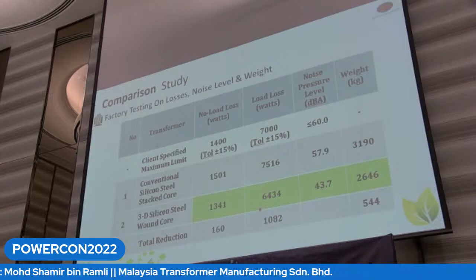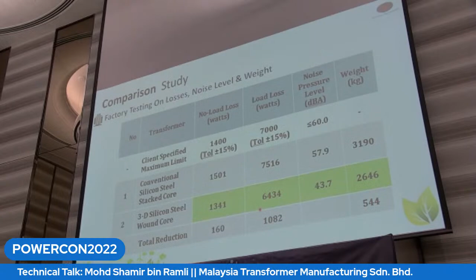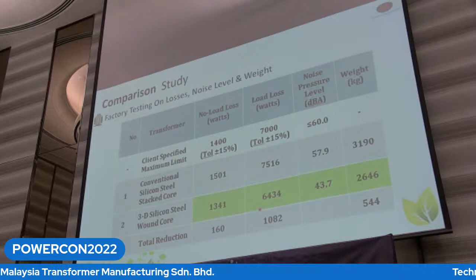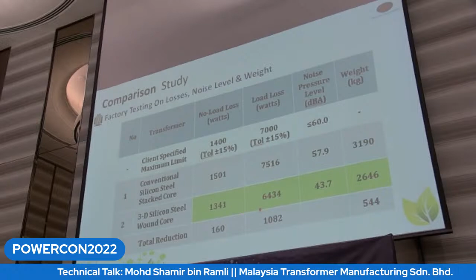The noise pressure is 43.7, which is much lower than the conventional transformer, and the weight is only about 2,646. So there will be a lot of reduction if we do a comparison on this. You can see we have a saving of about 160 watts for the no-load loss, 1,082 watts for the load loss, and 544 kilograms for the weight.